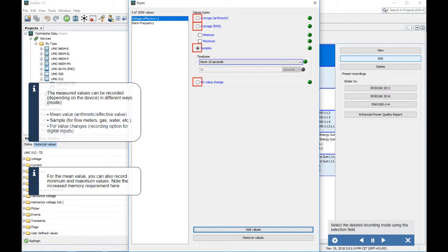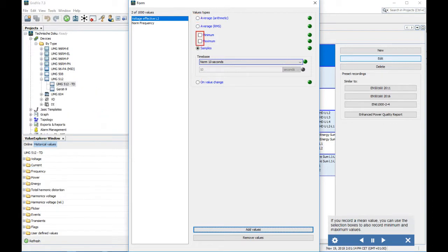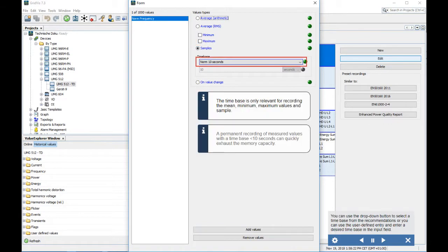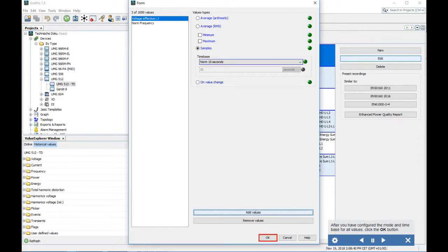For the mean value, you can also record minimum and maximum values — note the increased memory requirement. Select the desired recording mode using the selection field. If you record a mean value, use the selection boxes to also record minimum and maximum values. The time base is only relevant for recording mean, minimum, maximum values, and samples. A permanent recording with a time base less than 10 seconds can quickly exhaust the memory capacity. Use the drop-down button to select a time base from the recommendations, or use the user-defined entry to enter a desired time base. After configuring mode and time base for all values, click OK.